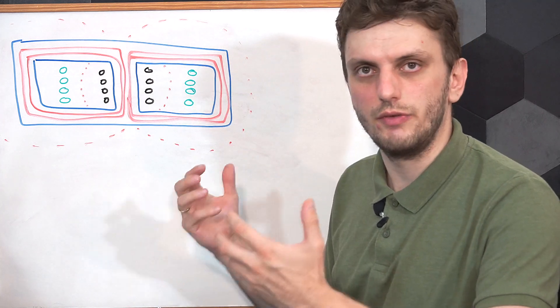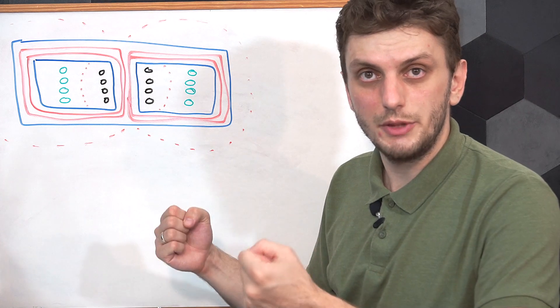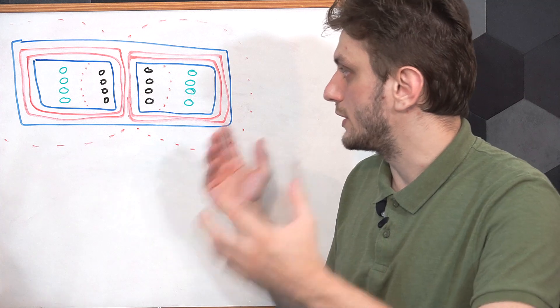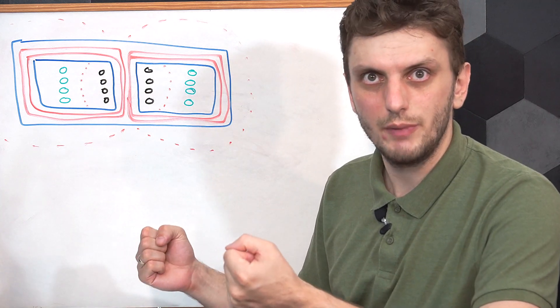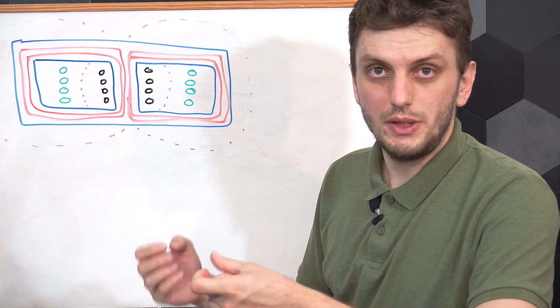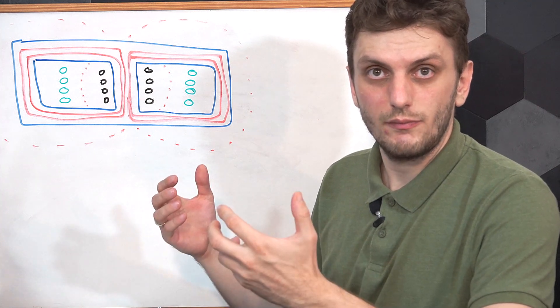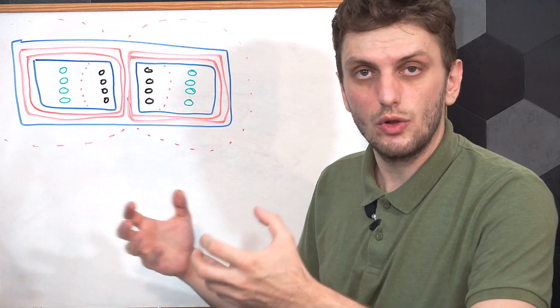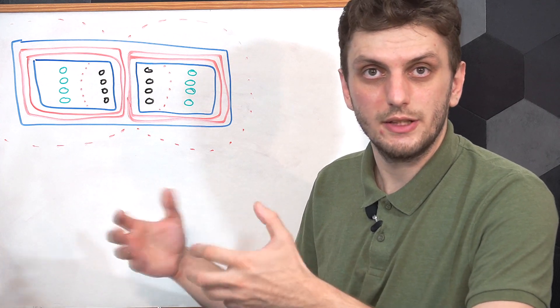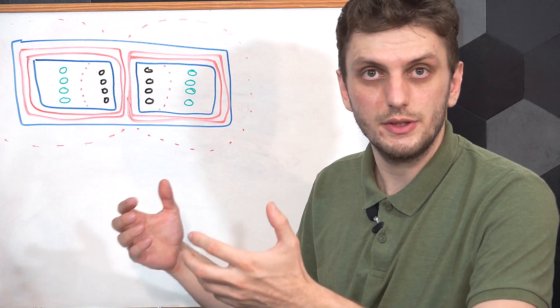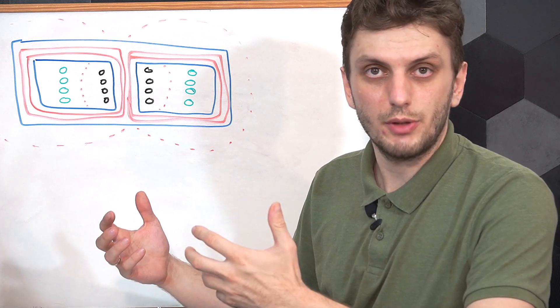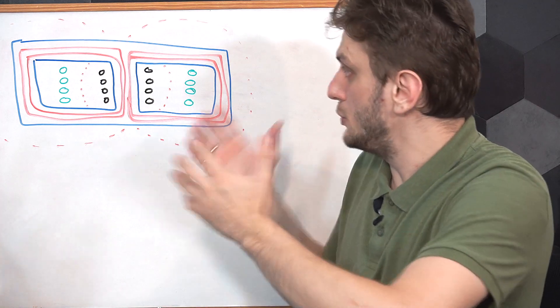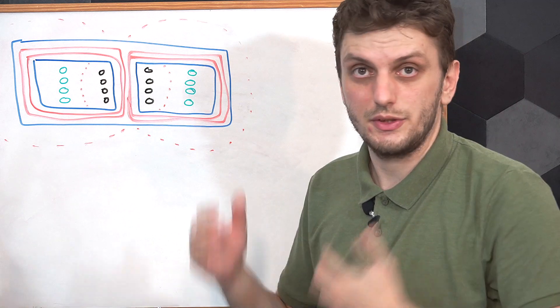And especially in very high power transformers, these external emissions can have a direct effect on circuitry around the transformer. So in extreme cases causing the circuitry to malfunction. And they can also be the direct cause of failed emissions tests, either by the direct emissions levels or by inducing other secondary effects like common mode currents and causing problems in that way. So it's sometimes very important to do something about these fields going outside of the transformer.